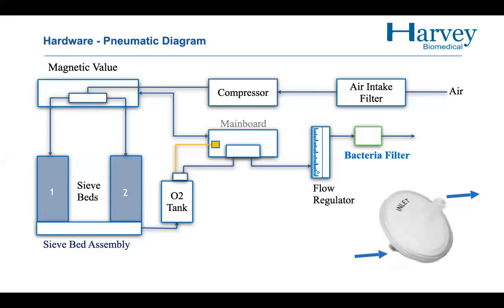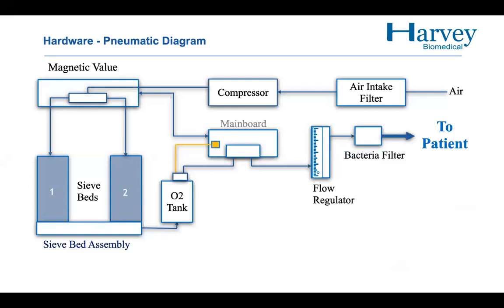Before the oxygen reaches the patient, it passes through the external humidifier bottle containing distilled water. The humidifier bottle is not shown in the block diagram because it is placed outside the machine. Oxygen passing through the distilled water becomes humidified. This is essential because the air has passed through the compressor and other hot electronic components, losing its humidity — if dry oxygen is inhaled, it dries the nose, lungs, and airways, causing damage.